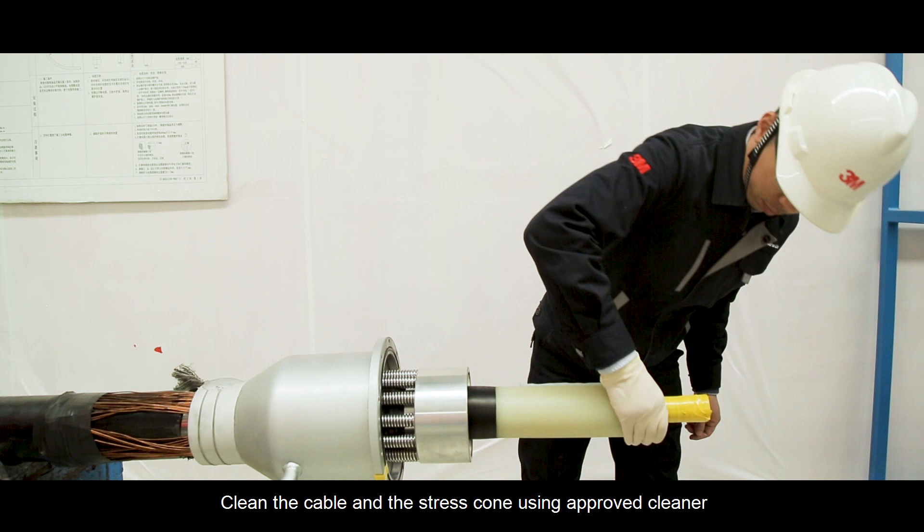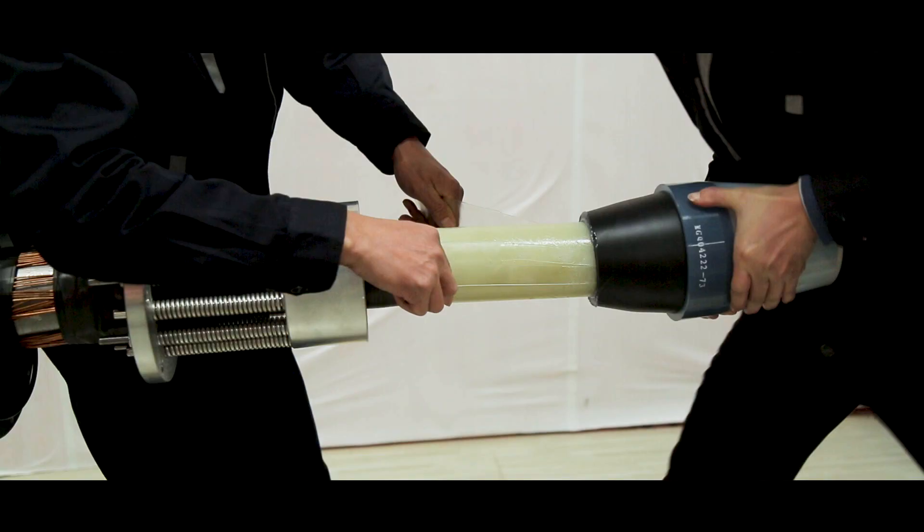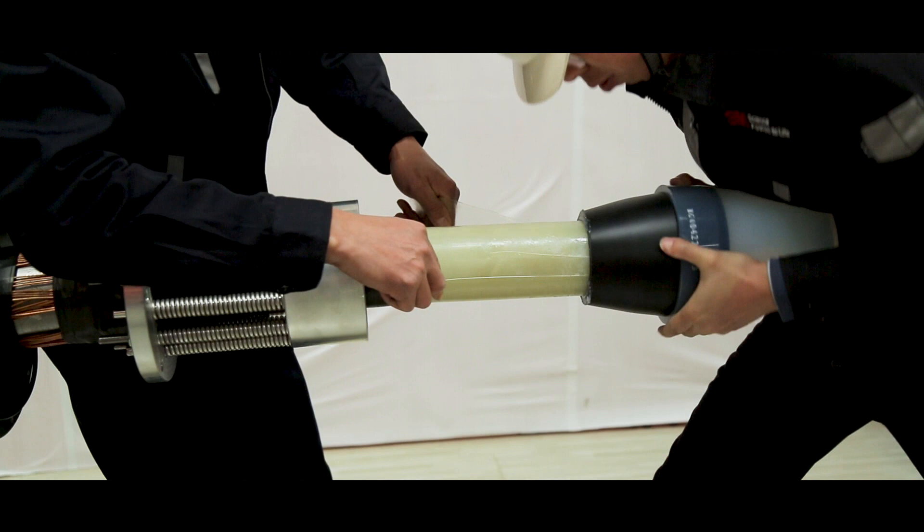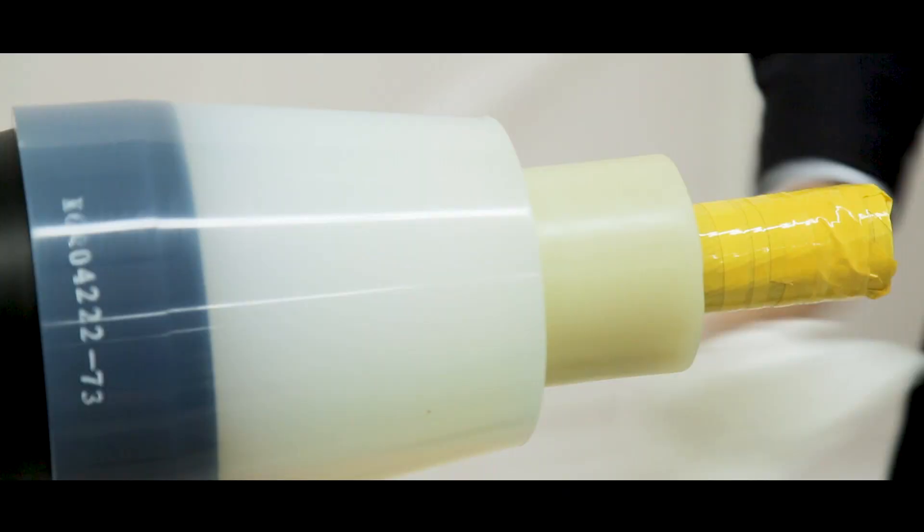Clean the cable and the stress cone using approved cleaner. Apply silicone grease on the insulation and the bore of the stress cone. Slide the stress cone onto the cable and stop at the mark. Remove the excess grease and clean the cable and stress cone.